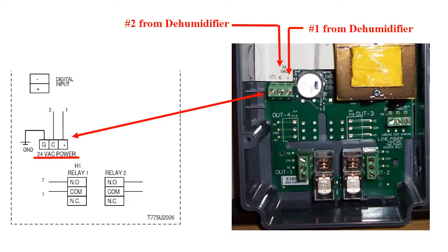On the power strip schematic, you will notice a number 1 next to the wire protruding from the positive terminal. This means that terminal connects to a number 1 terminal on the dehumidifier. The number 2 next to it on the C, or common, means that it is to be connected to a number 2 terminal, and so forth for all connections. An earth ground is required on the third terminal of the power strip.